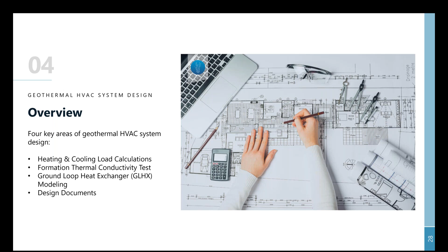The load calculation portion of the HVAC system design is extremely critical. Load calculations matter for any design, but for geothermal you really have to drill down deep. It's not just the peak loads you may find—what is the peak cooling load, 100 tons, what is my peak heating—we're not just looking at one point in time, but at how the building performs annually over the entire year.